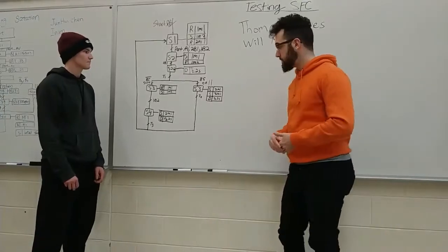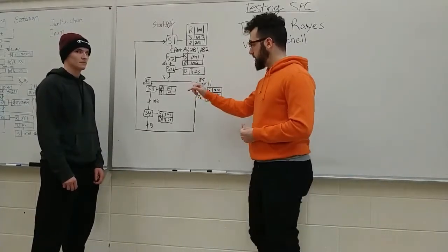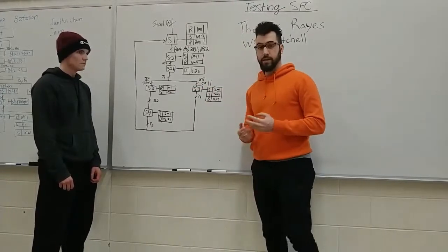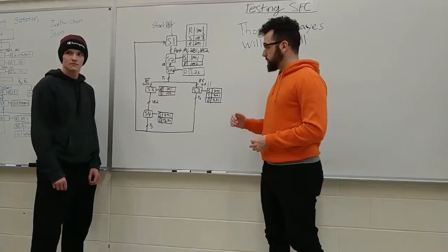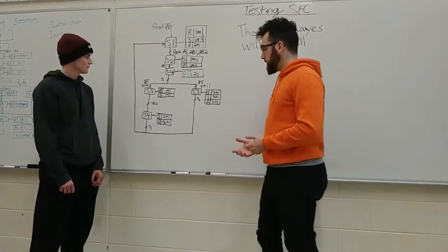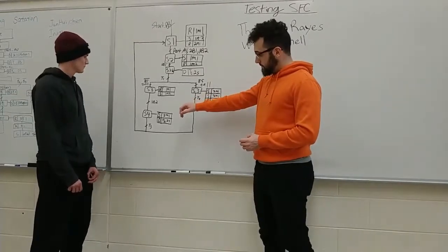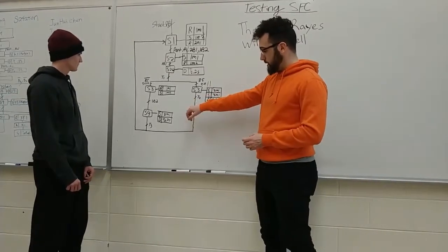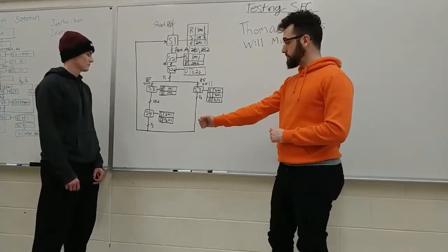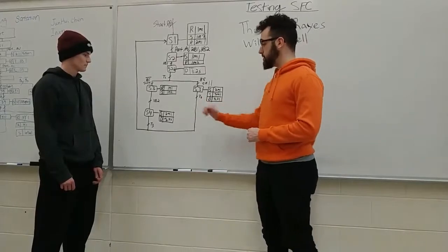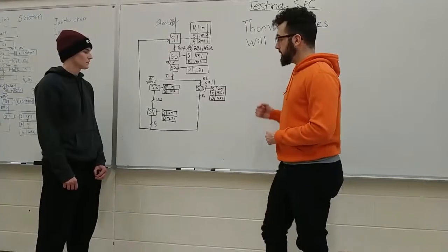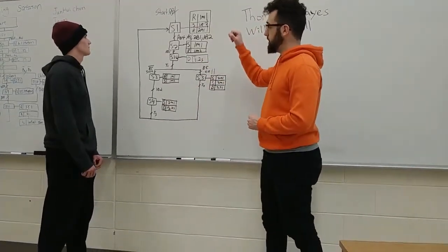short or tall. If the piece is short, 1M1 is reset and 1M2 is set. This will bring the lift down to the bottom position. Once it reaches the bottom position, 1B2 will detect this and send a signal. So then in step 4, 2M1 will be set. This is the pusher. This will extend the pusher. Once the pusher is extended, a time delay of 2 seconds starts.